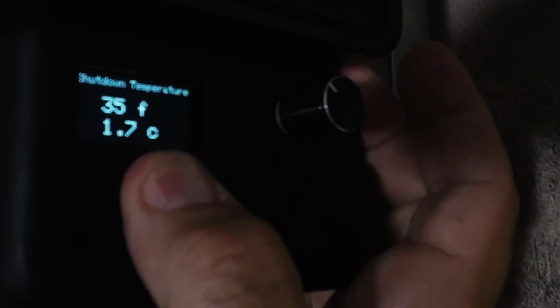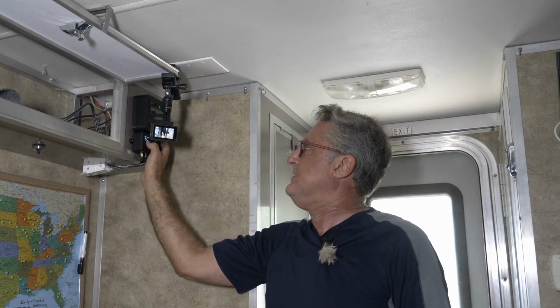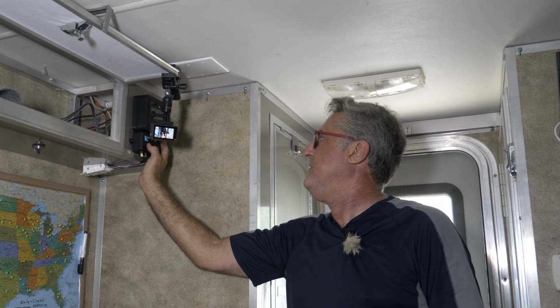So go into that. It's set for 35 degrees Fahrenheit. When the temperature goes below 35 where the sensor is, batteries are off, and they stay off until I think it goes above 40. I think it's like a 5-degree differential. You can do that in Celsius too. It's 1.7 degrees Celsius.